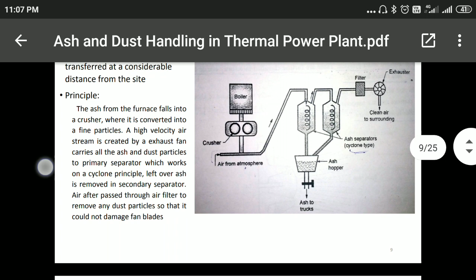The advantages of the pneumatic handling system are that it can handle abrasive and fine ash particles, and it removes all types of ash in a dry state, so there is no problem of corrosion, because we are using air, not water. The limitation is high maintenance cost due to more components than the hydraulic system, because we are using separators, filters, exhauster fans, and a blower to carry the air at high speed. Because of so much equipment, it occupies more space than the hydraulic system.